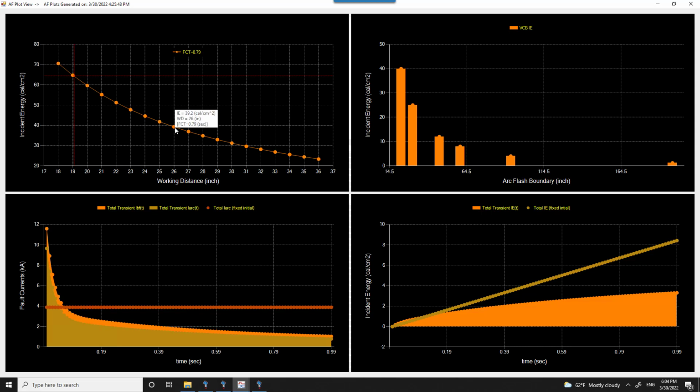So the bottom line is, with the use of the calculator along with the protection and coordination settings for arc flash, the results of incident energy could be easily evaluated without rerunning the study in ETAP for all the different facilities or all the different faulted locations per se.